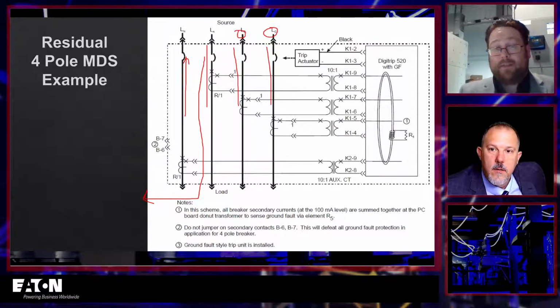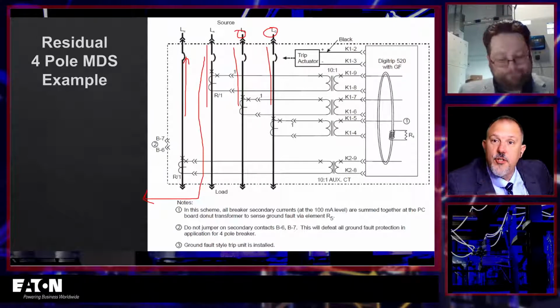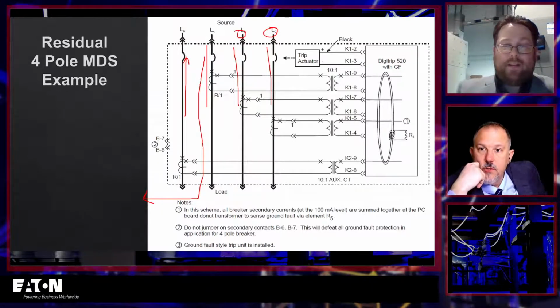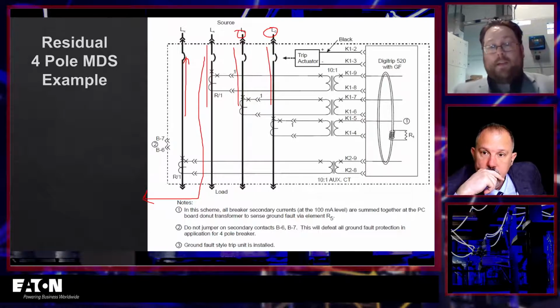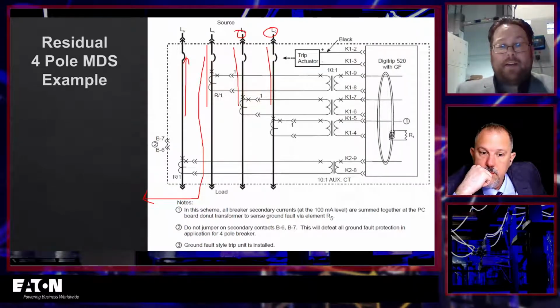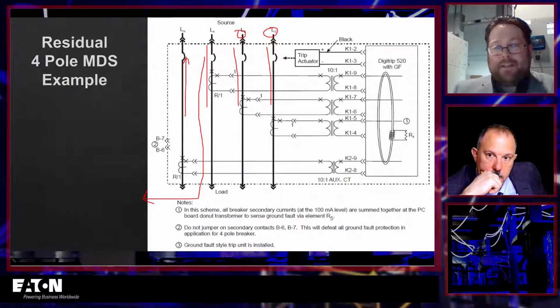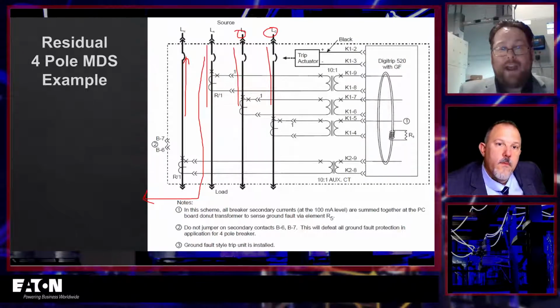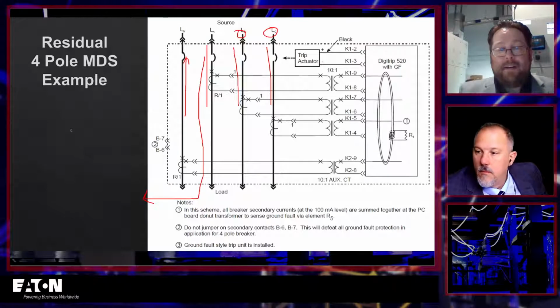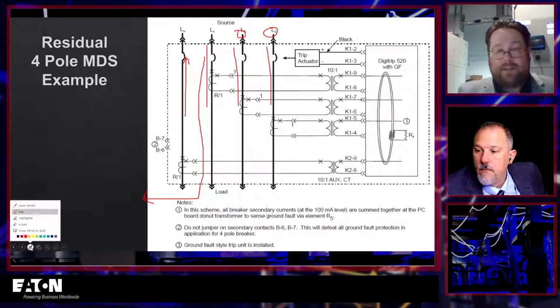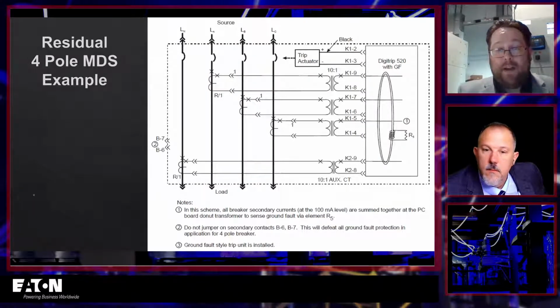That should be a no trip. So there's a trip and a no trip, so you've got to verify that imbalances won't trip the breaker, right? Yes. We want to make sure all the polarities are correct because just confirming it tripped didn't actually confirm all of your CT hookups. So think about this. You injected current through phase A, right? And it didn't go back through the neutral conductor, the neutral CT, the opposite direction. That would be a trip. We'd be happy with that. But you didn't actually confirm the neutral CT was connected properly.